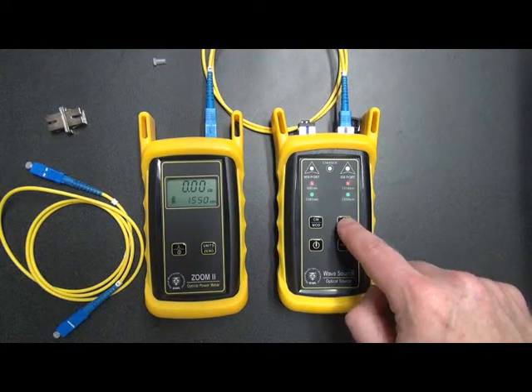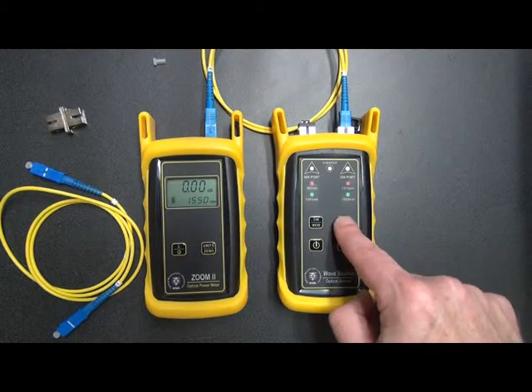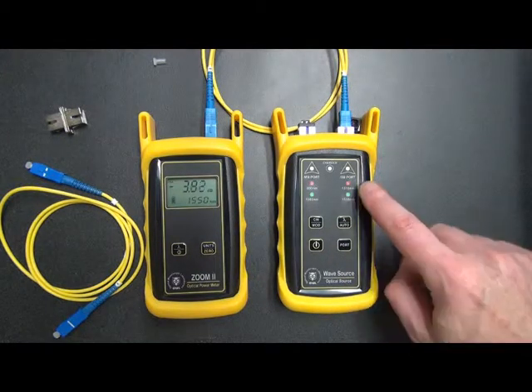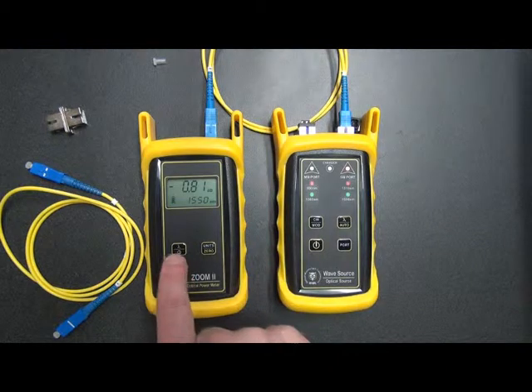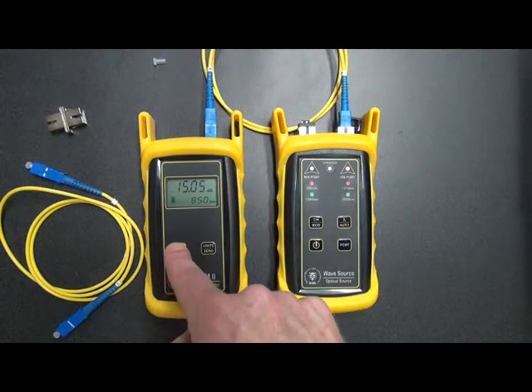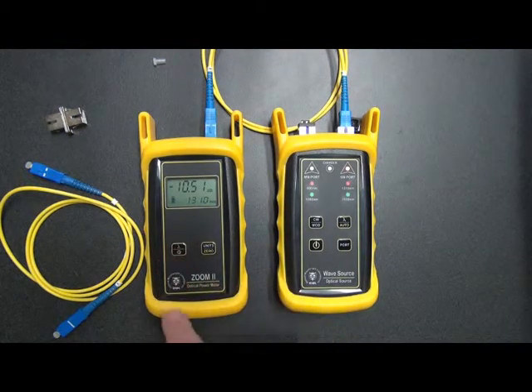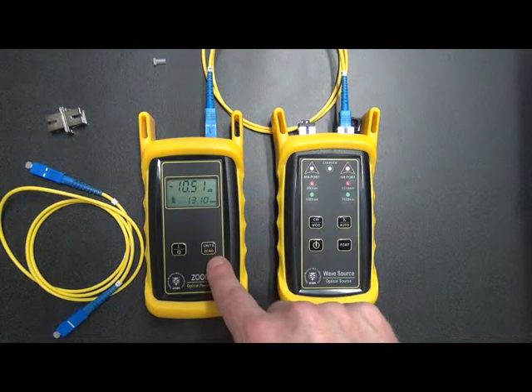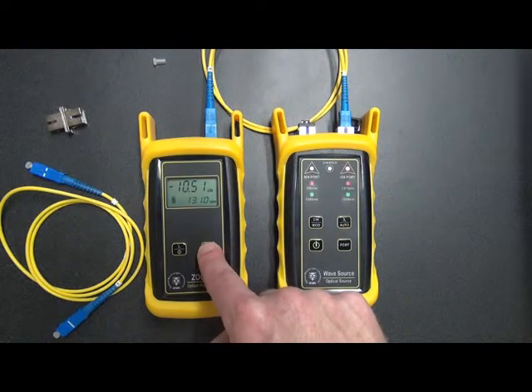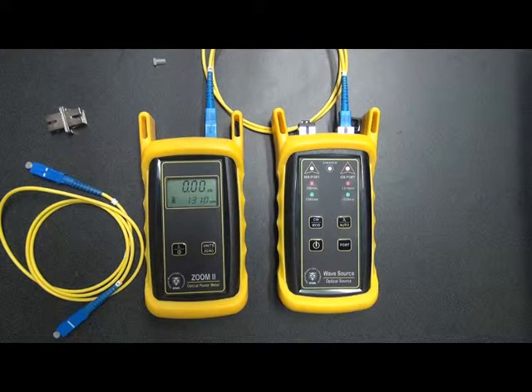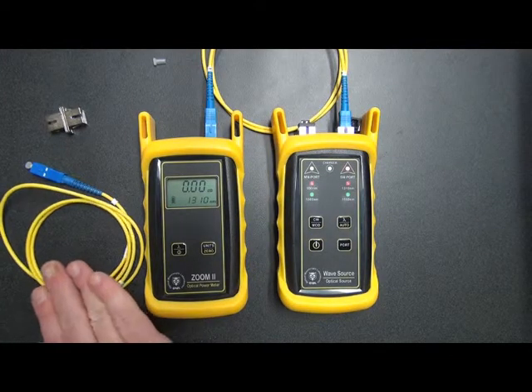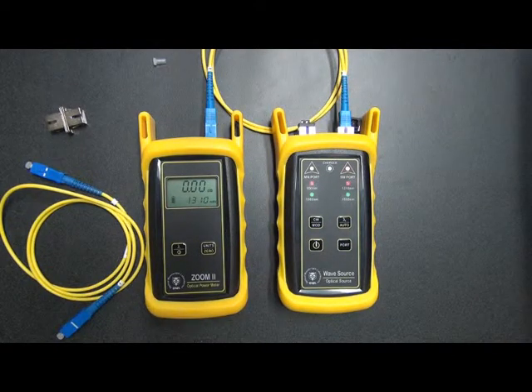But we also want to zero out at 1310, so we press the wavelength button on the WaveSource to switch to 1310, and then we press the wavelength button until we get to 1310 nanometers, and then we again press and hold the 0 button. All right, and we see 0 dB. So what we've done is we've zeroed out both wavelengths, and now we can check this second cable.